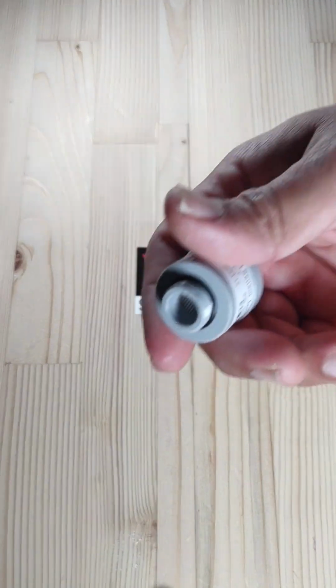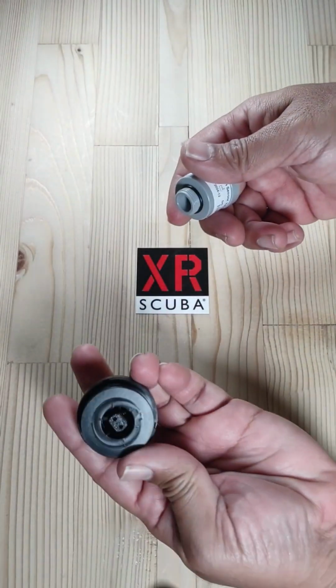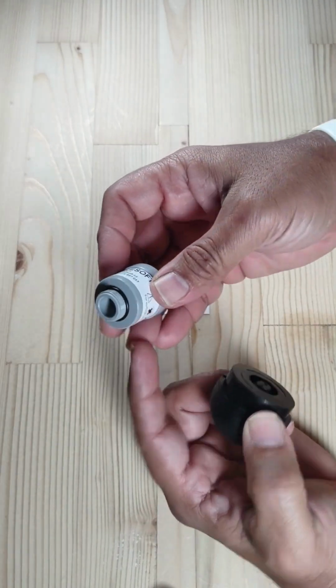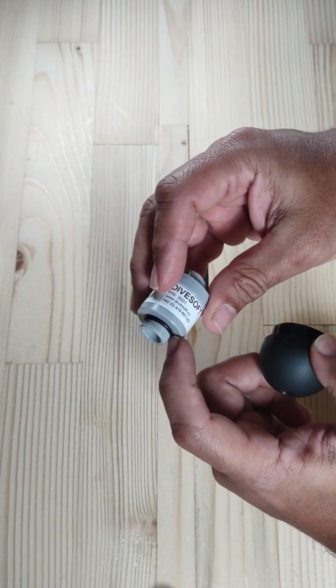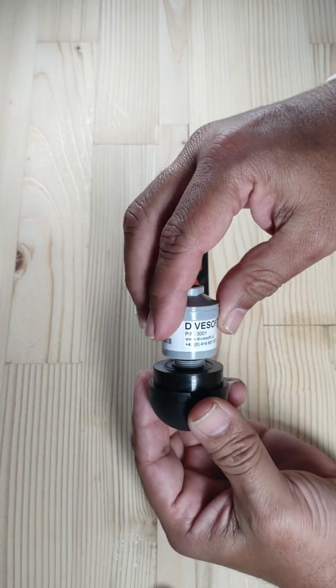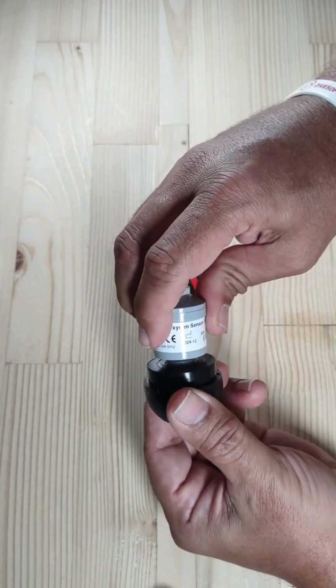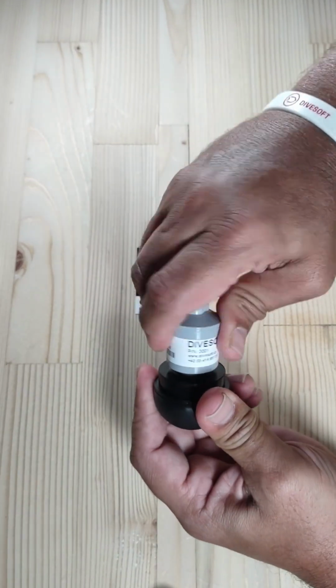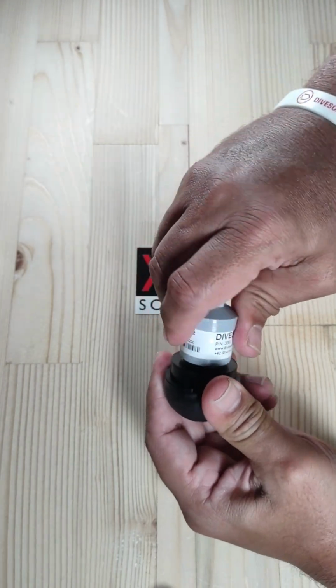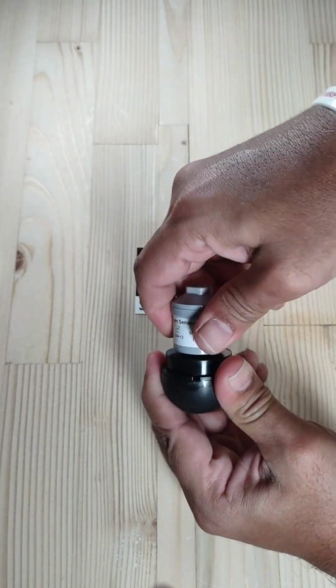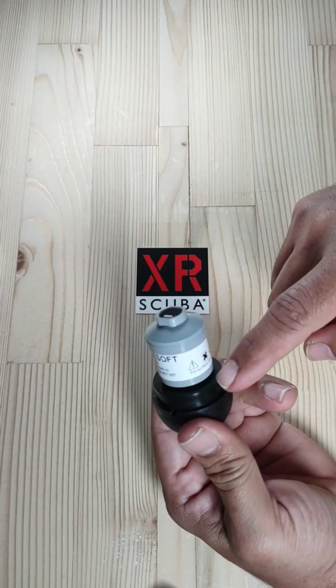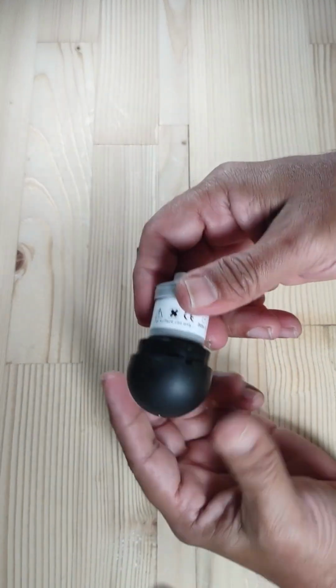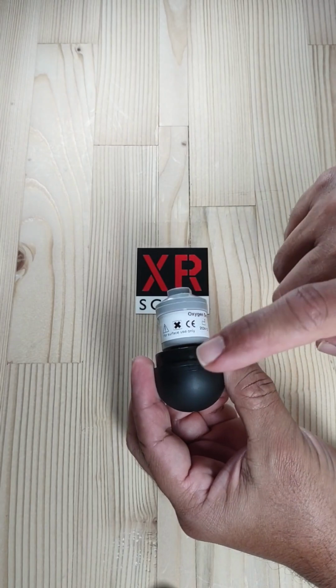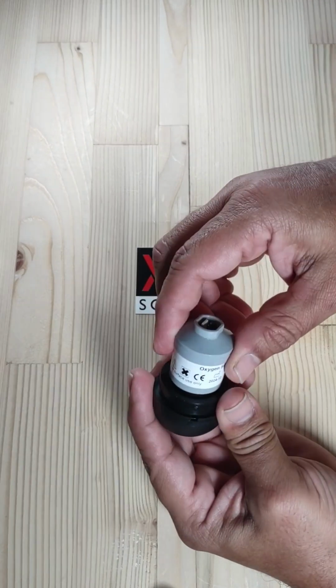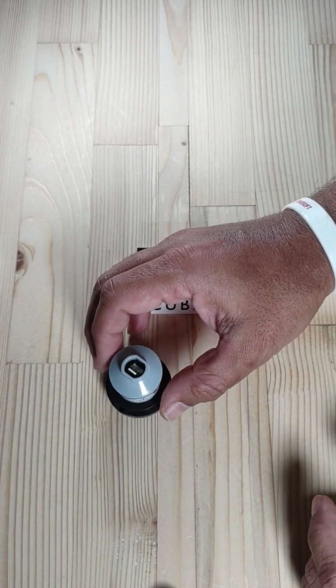So here's your sensor, and then you get your head, and you want to screw it in until this O-ring is touching here. That helps create a better seal, which helps with analysis. So again, you don't need any tools for this. Just screw it in gently until the O-ring is touching. Do not over tighten. You might break the sensor or you might damage the head. Okay. Once it's ready, it should look like this.